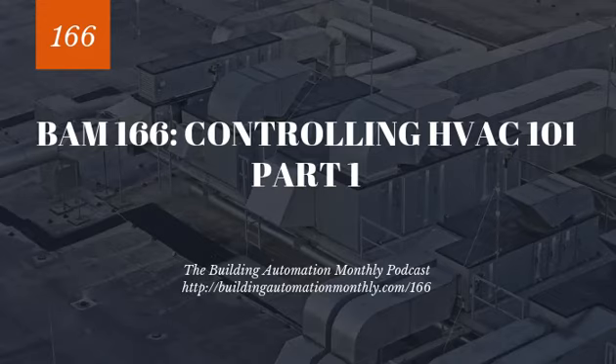They will tend to be driven by a single temperature sensor per VAV. I'm not saying that's the best way to do it, and I'm not saying that's how I recommend doing it. I'm just saying on average, that is how it's installed. So you've got this VAV box branching off of a main trunk line coming off of an air handler, and it balances the amount of air by opening and shutting the damper to control to an airflow set point.